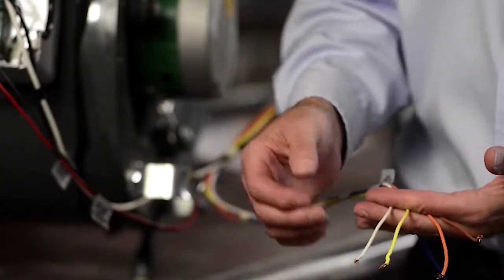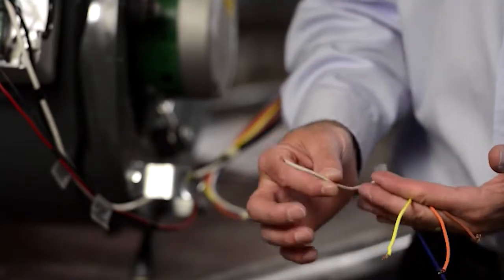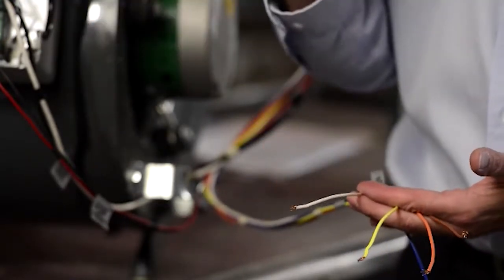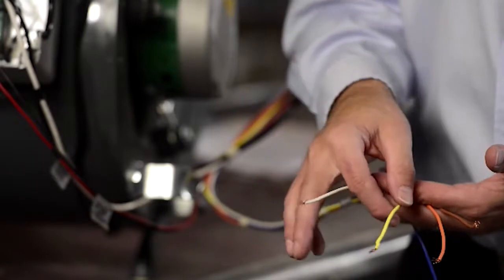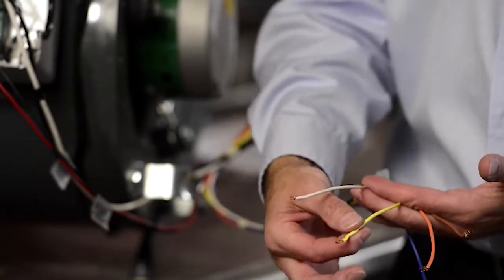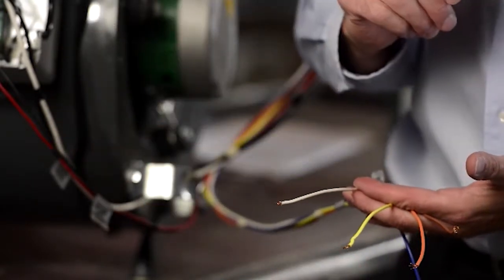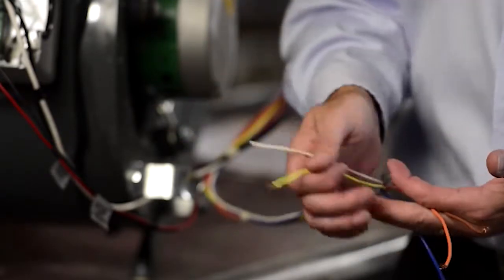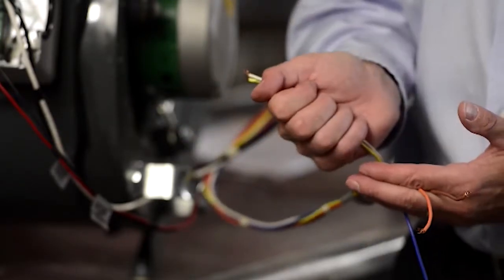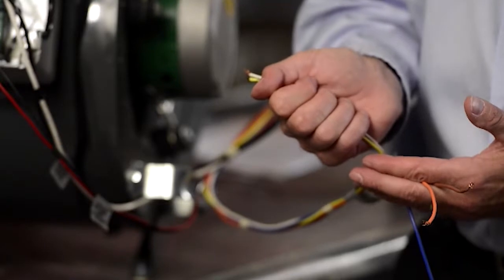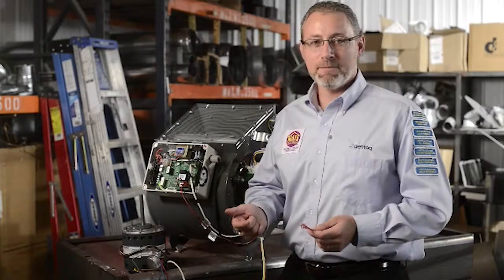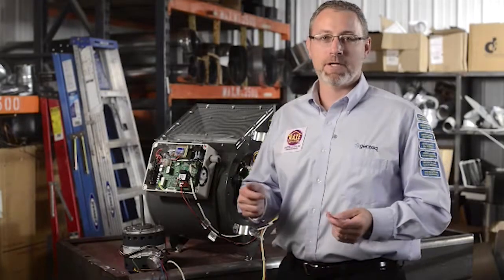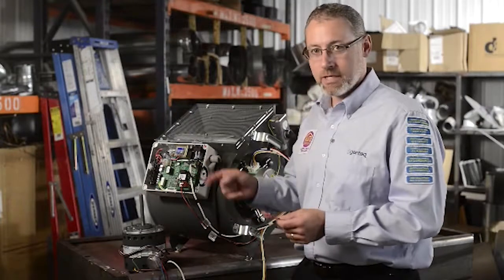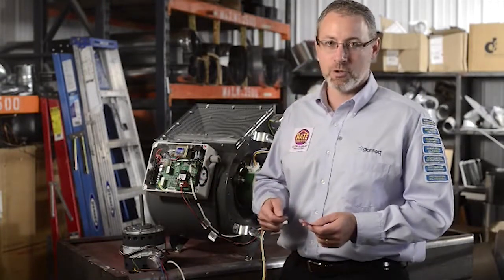If I wanted low speed for heat, I would connect the white wire to the heat terminal, which is usually labeled W. And if I wanted high speed for cool, I would connect this yellow wire to the cooling wire, which is usually labeled Y. When I'm all done, I would then tape off my other 2 unused speeds. So before we wrap up the electrical connections, let's talk about a couple of what-if scenarios. Because every system you work on isn't going to be a heating and cooling only system with just heat and cool taps on the control board.